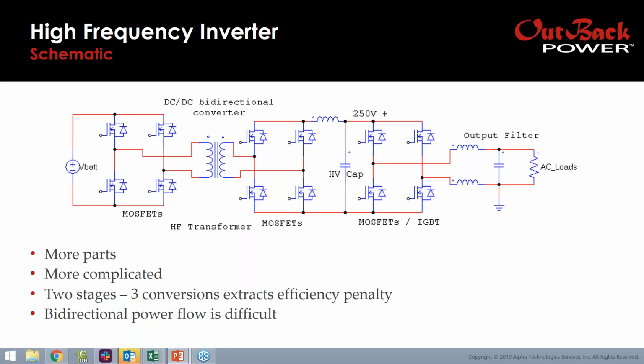This is a schematic of a high frequency inverter, and as you can see, there's a lot more going on in here. There are more parts, it's much more complicated. It takes 2 stages and actually 3 conversions to go from DC on the left-hand side to AC on the right-hand side. Typically, the DC is converted from a low voltage battery voltage up to a higher voltage, something intermediate between 250 and 400. And then that is converted again down into output. And they're often called high frequency inverters.